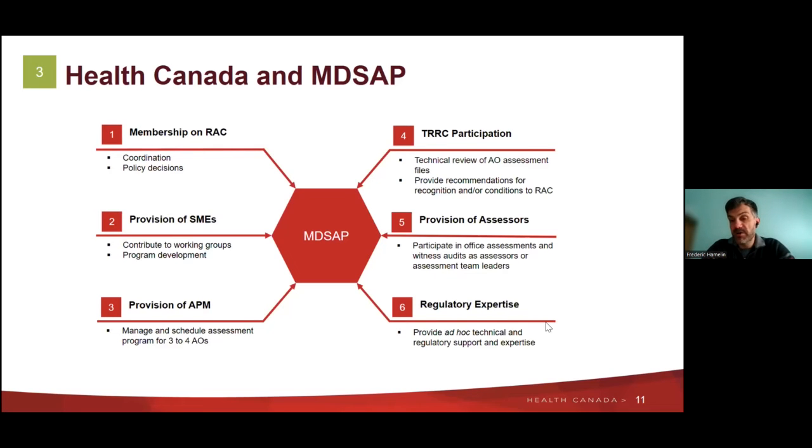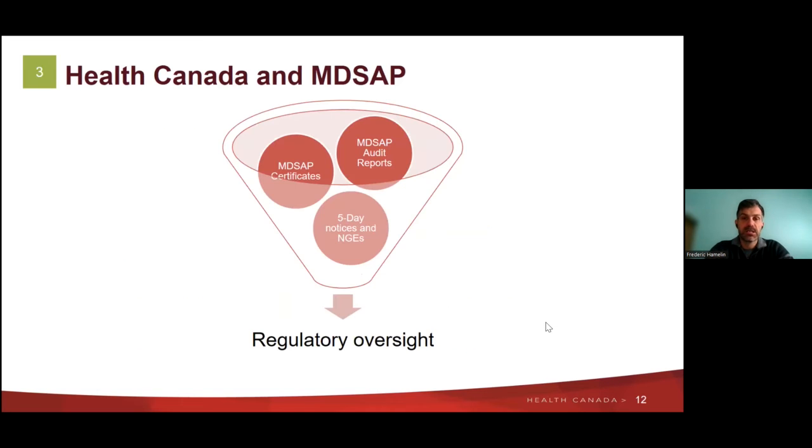And finally, we provide regulatory expertise. So there may be technical questions that come up within the program about Canadian regulations and how they apply, or the interpretation of whether a finding is a nonconformity or not based on our regulations, or tailoring program requirements to meet our needs. So these are all the ways that we fit into MDSAP.